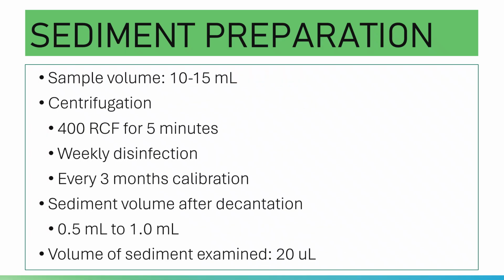Again, just to sum up, your sample volume is 10 to 15 ml, and centrifuge. Please note that the centrifuge must be disinfected weekly, and the centrifuge must be calibrated every 3 months.